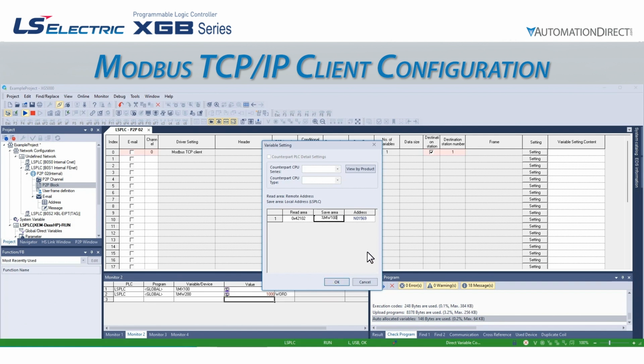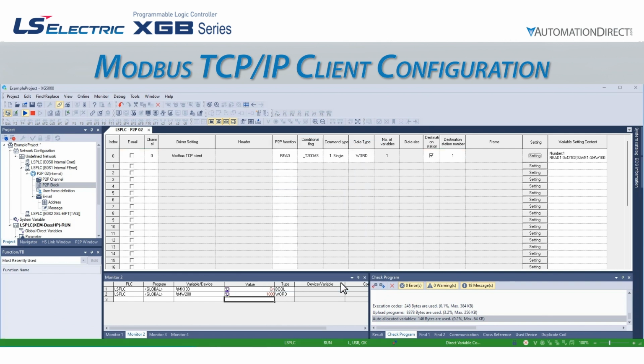That address was arbitrarily selected and can be any available direct variable address. Because the %M range of memory addresses is reserved for functions just like this, we strongly recommend using that range to avoid unintentionally overwriting PLC or communication data. We have now set up our Modbus read message.